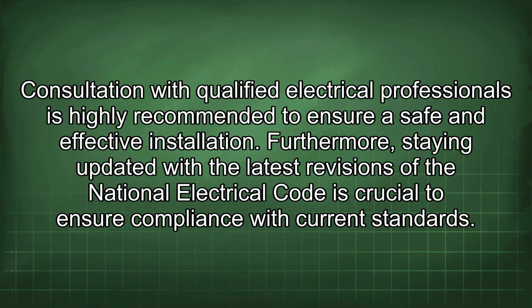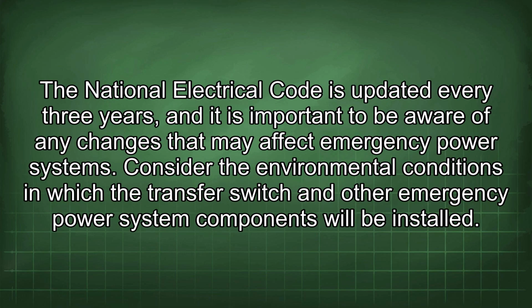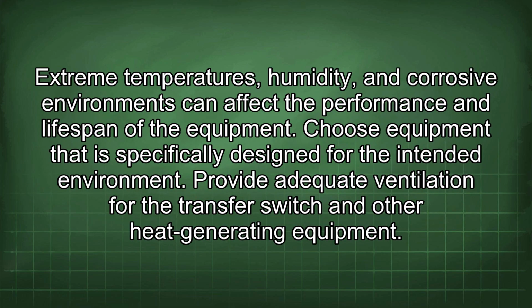Furthermore, staying updated with the latest revisions of the National Electrical Code is crucial to ensure compliance with current standards. The National Electrical Code is updated every 3 years, and it is important to be aware of any changes that may affect emergency power systems. Consider the environmental conditions in which the transfer switch and other emergency power system components will be installed. Extreme temperatures, humidity, and corrosive environments can affect the performance and lifespan of the equipment. Choose equipment that is specifically designed for the intended environment.